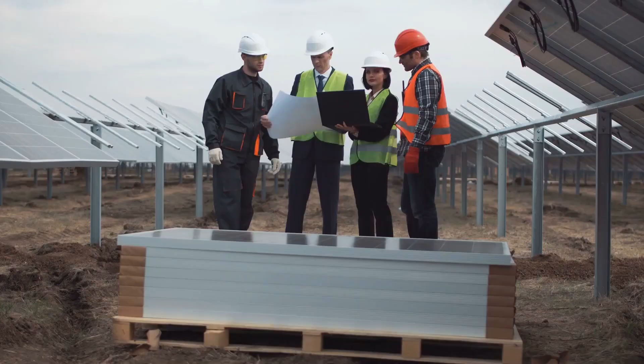Not integrating commissioning into your procurement processes already limits your ability to be successful during on-site testing, since equipment will be arriving at site with defects and deficiencies that should have been caught in the factory. Control systems are complex and always cause issues at the end of projects, and if these critical deliveries are not integrated and tested properly in the factory, your project will experience significant delays while your logic programming is sorted out on site.